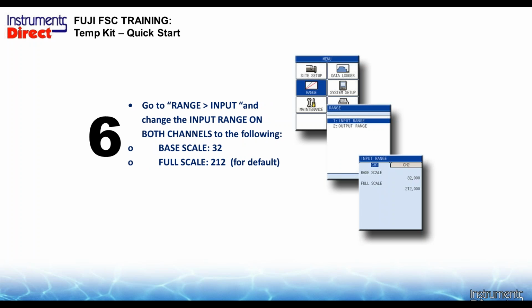And as far as the range input, this should be pre-programmed by us, but if it isn't, our temp kit is designed that the base scale is 32 and the full scale is 212, and that's our basic defaults. You do not need to calibrate this device. It is ready to go out of the box.